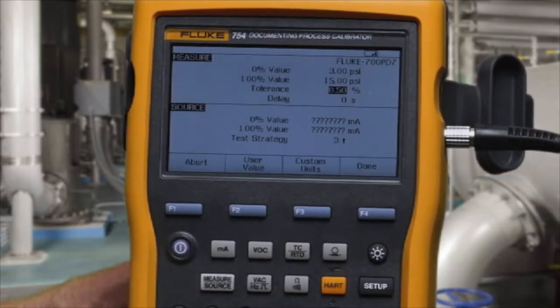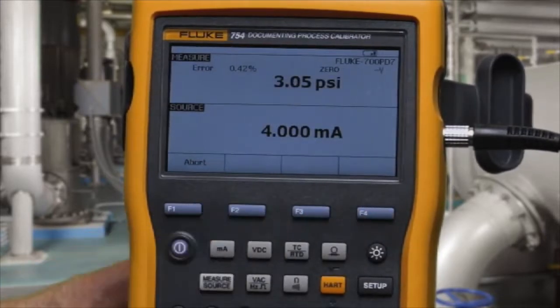while sourcing 4 to 20 milliamps. We select auto test, and the calibration test will automatically perform. The milliamps are applied, the pressure is measured, error is calculated, and it's recorded to memory.